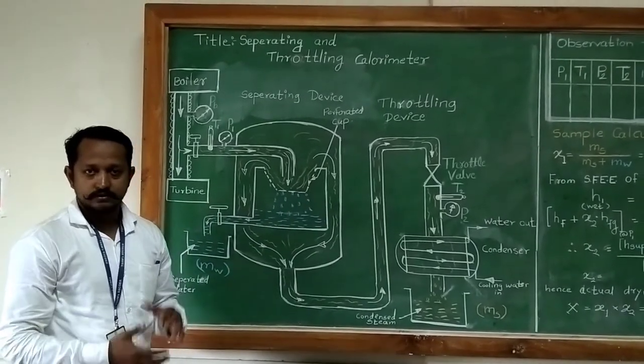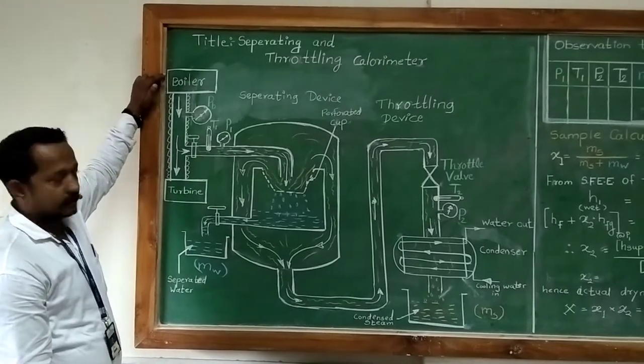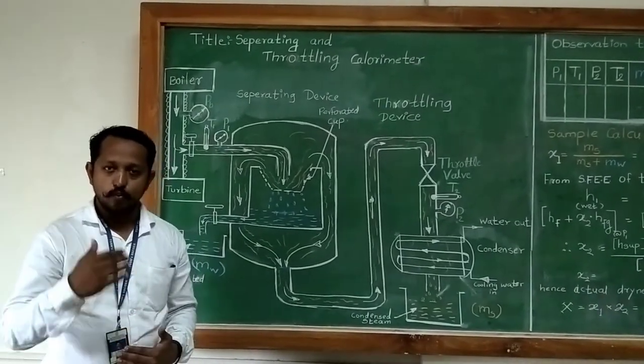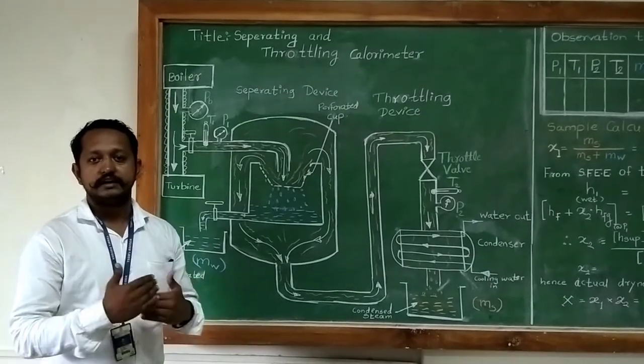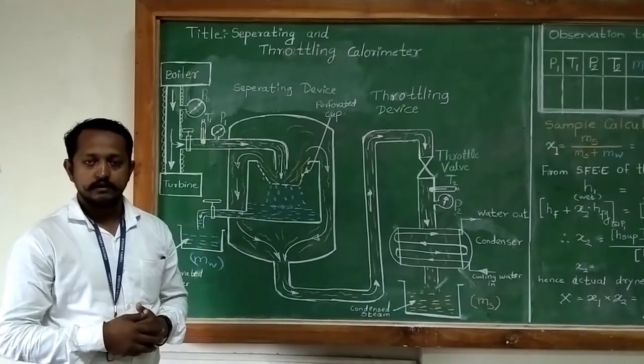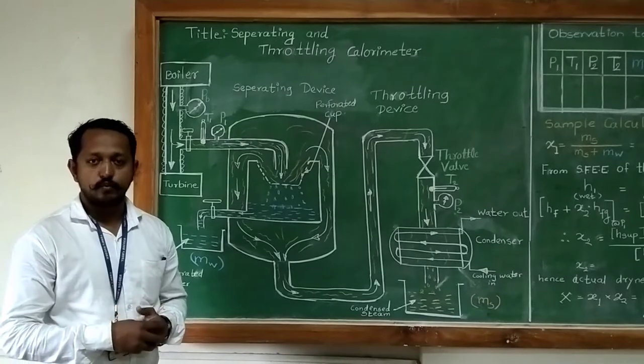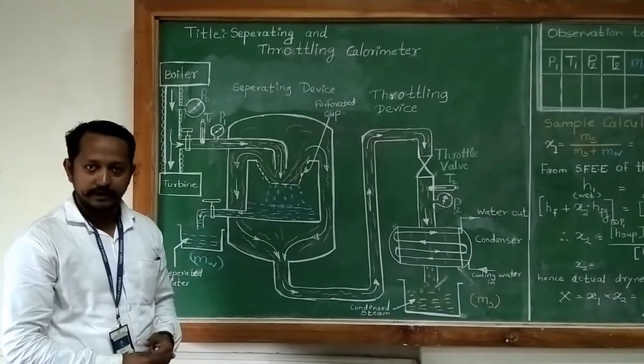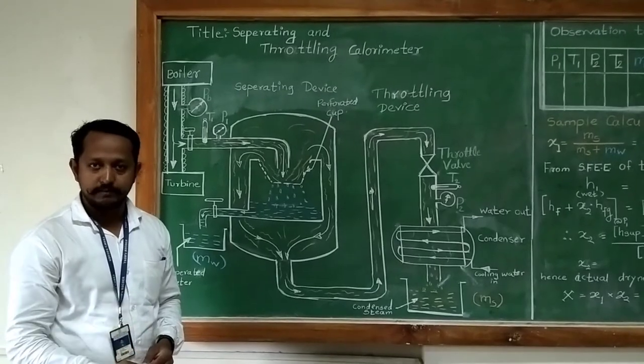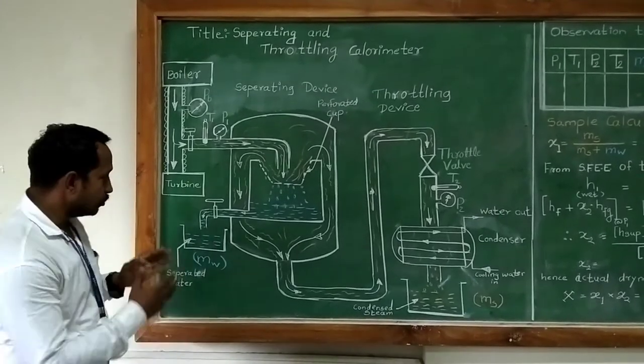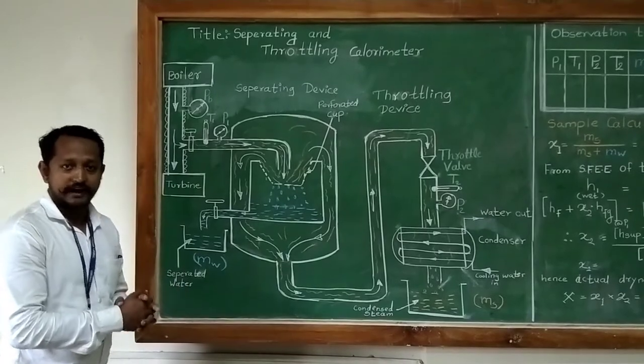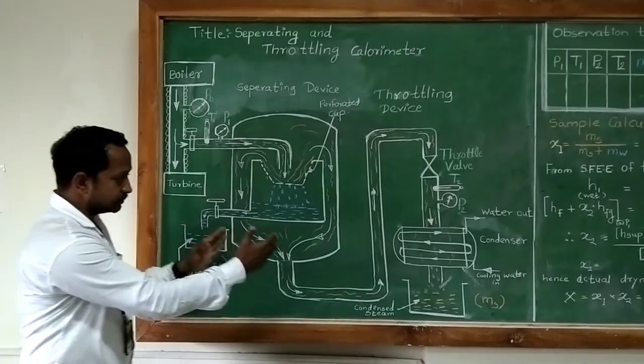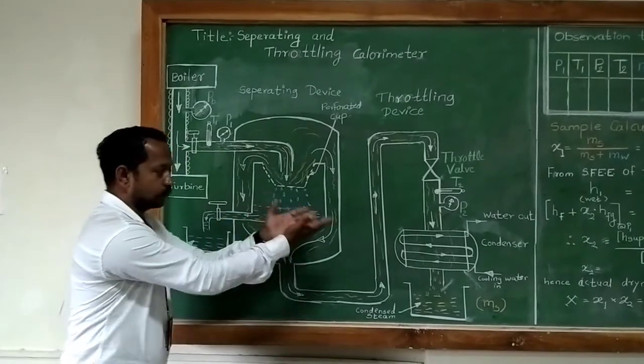We know the steam is generated in the boiler and it is supplied to the turbine. But before supplying it to the turbine, one should ensure what is the dryness fraction of the steam. The dryness fraction required for steam whenever it is supplied to the turbine should be around 80% or more. So, to know the exact amount of dryness fraction, one should use some device like the separating calorimeter.